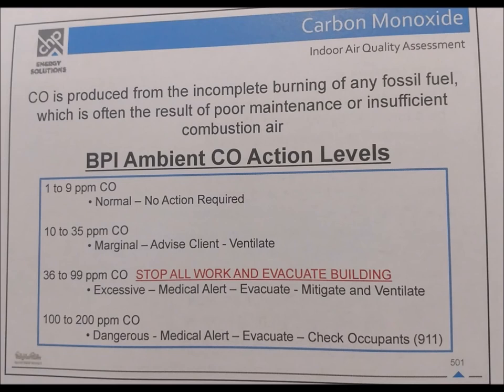Carbon monoxide (CO) is produced from the incomplete burning of any fossil fuel, often the result of poor maintenance and insufficient combustion air. BPI ambient CO action levels: 1–9 ppm — normal, no action required. 10–35 ppm — marginal, advise clients and ventilate. 36–99 ppm — excessive, stop all work, evacuate building, medical alert, mitigate and ventilate. 100–200 ppm — dangerous, medical alert, evacuate, check occupants, call 911.